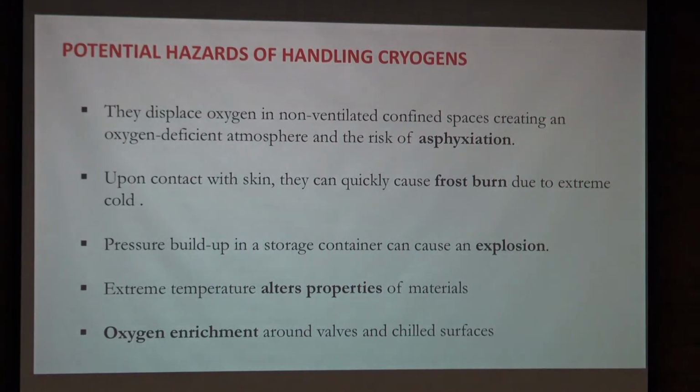Okay, we've already mentioned the main danger when handling cryogenic liquids is that when they evaporate, they expand fairly dramatically, and they can create an oxygen deficient atmosphere and present the risk of asphyxiation, even though the gas is completely non-toxic. When it displaces oxygen, that still creates a hazard.